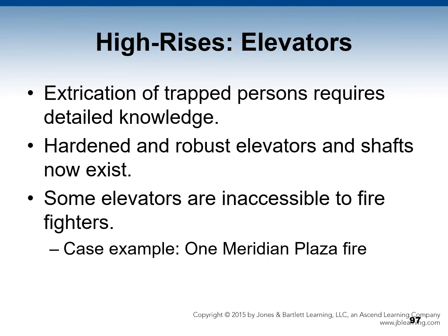Let's discuss elevators in high-rises. Extrication of persons trapped in stalled elevators requires a detailed knowledge of elevator construction and operating systems. In the past, the use of elevators for fire evacuation has been considered dangerous and is universally warned against by signs placed in or near elevators. Since the World Trade Center disaster, a new generation of so-called hardened and robust elevators and shafts is being developed for evacuation purposes. In some fires, all elevators may be totally unavailable to the fire department.